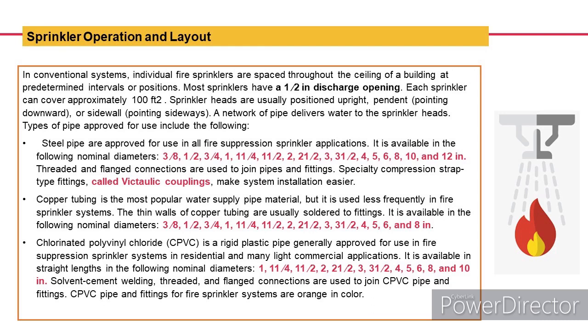Copper tubing is the most popular water supply pipe material, but it is used less frequently in fire sprinkler systems. The thin walls of copper tubing are usually soldered to fittings.